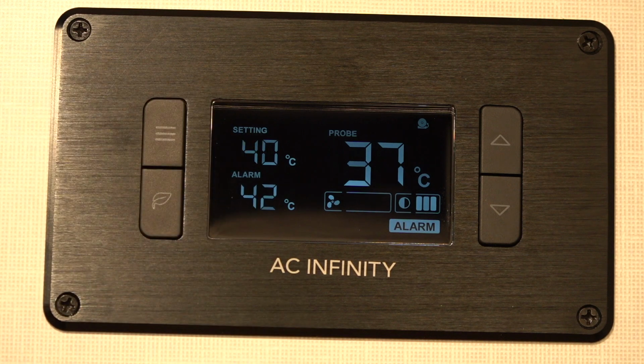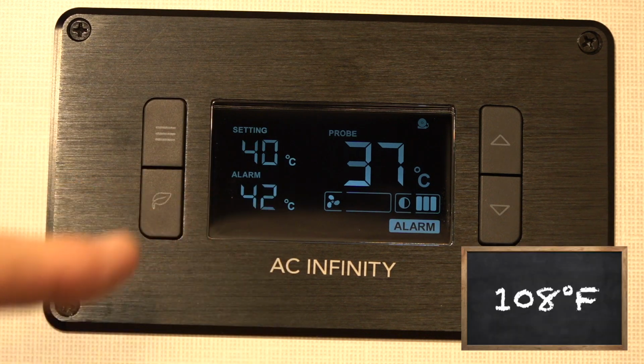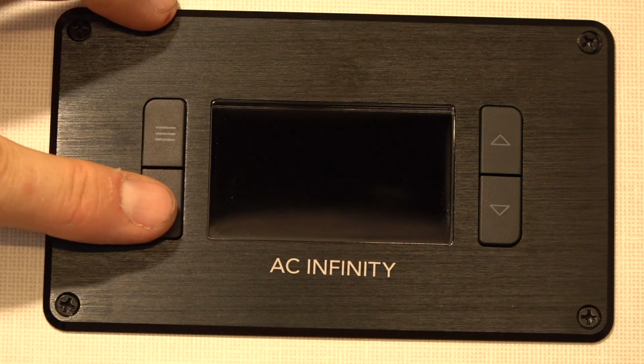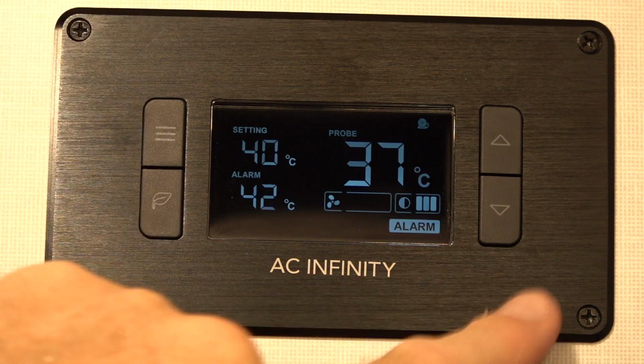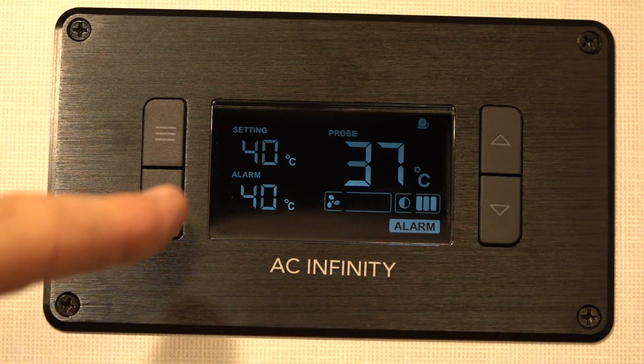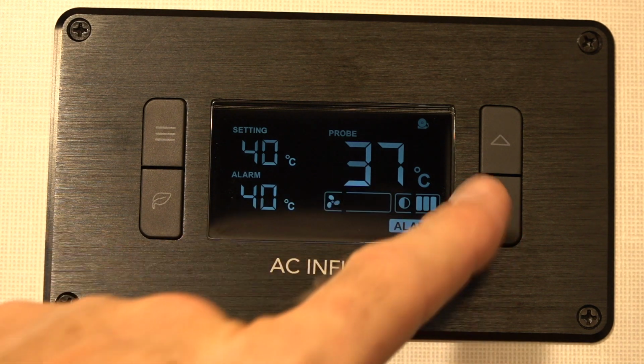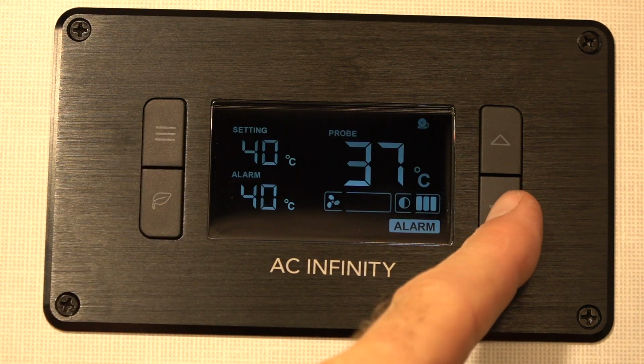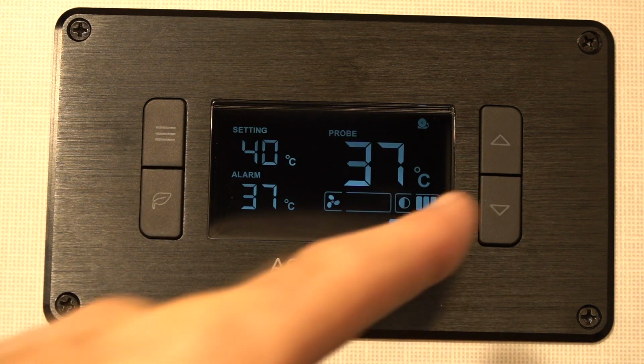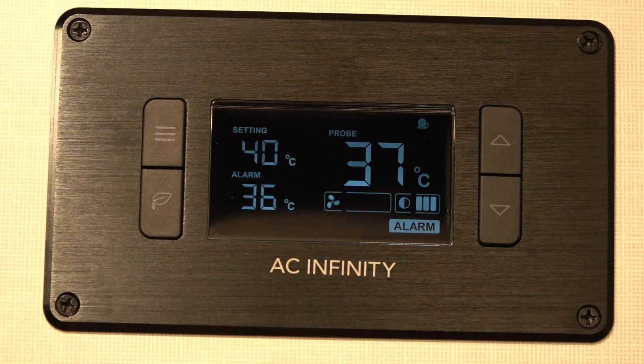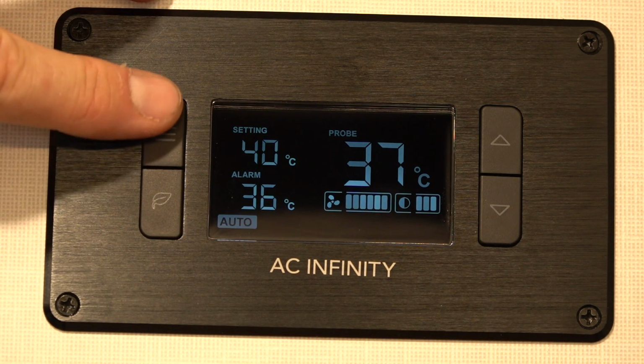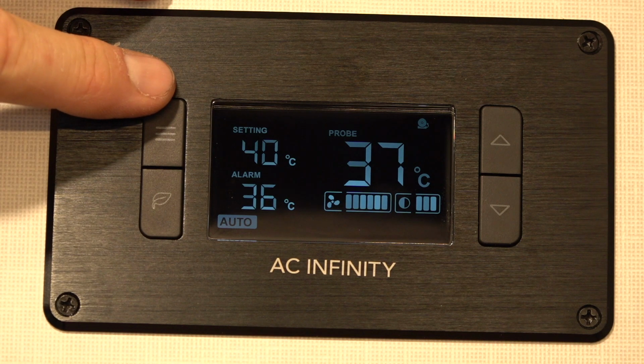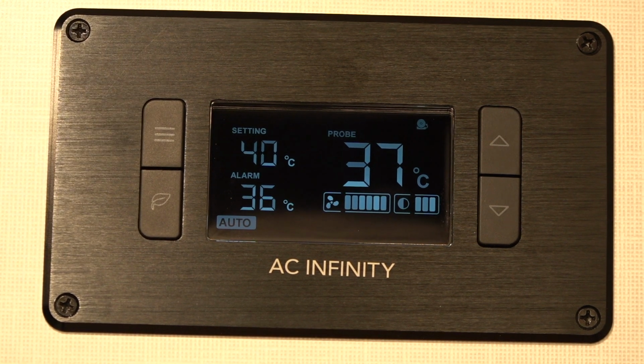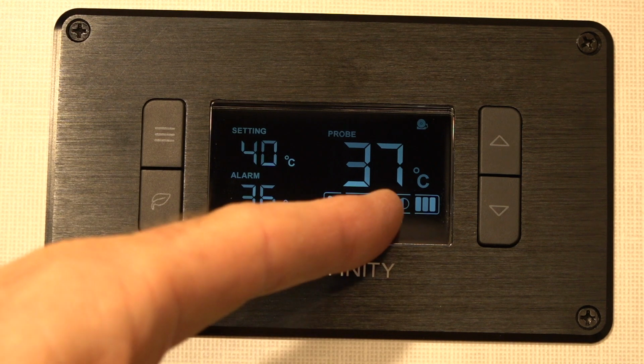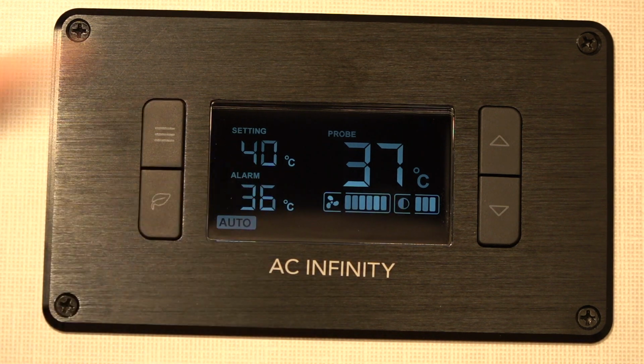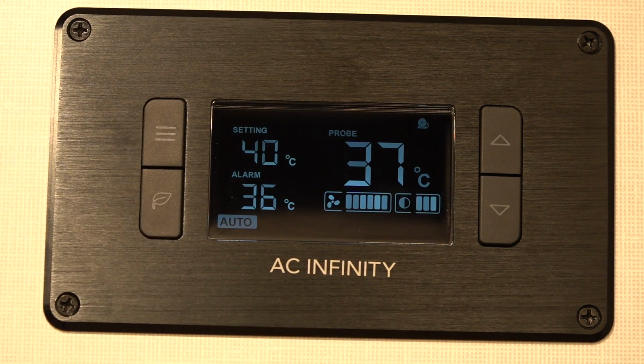And then I can set an alarm temperature, so it's 42 degrees right now. If I can, oops, turned it off, sorry. I can lower the alarm temperature, and when the probe temperature reaches the alarm temperature, then I should hear some sort of a beep. Not sure if you heard that. It is beeping now because the probe temperature is higher than the alarm temperature.